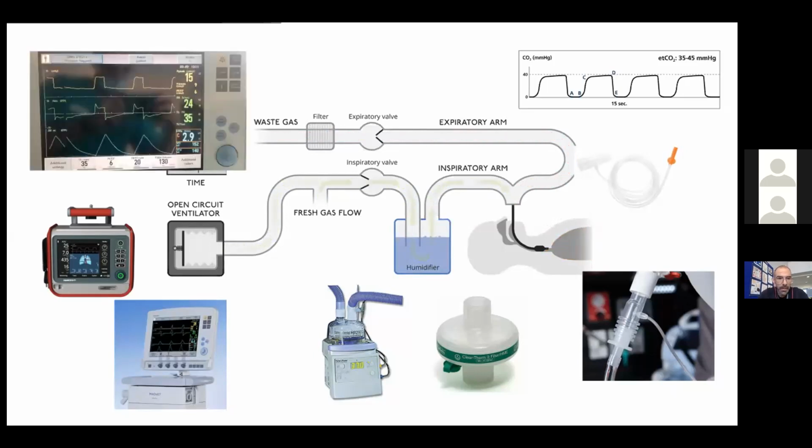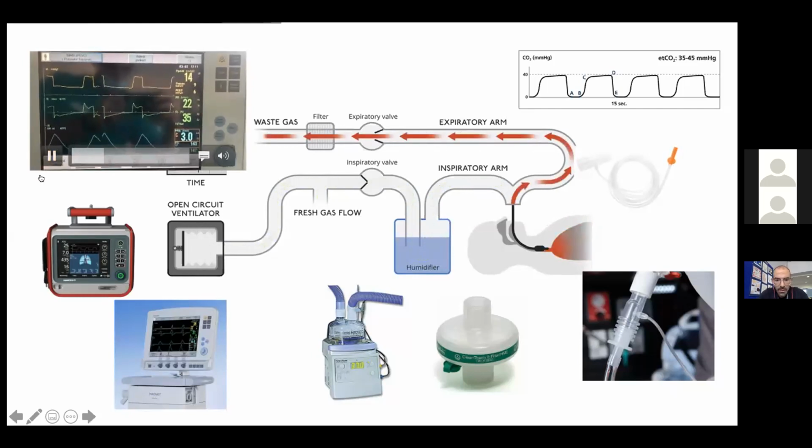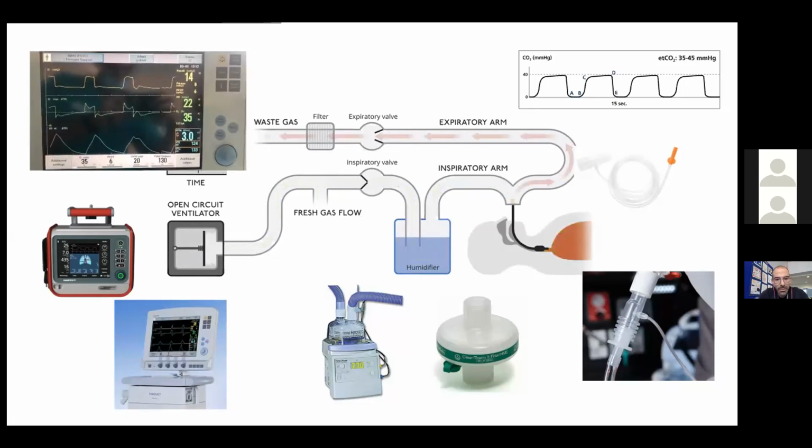And then we have the ventilator, which will give you these sorts of graphs. At the top you have pressure-time, in the middle you have flow-time, and at the end you have volume-time. This is how we monitor how well we are ventilating children. Some ventilators have different curves, but most of them have these three main curves.